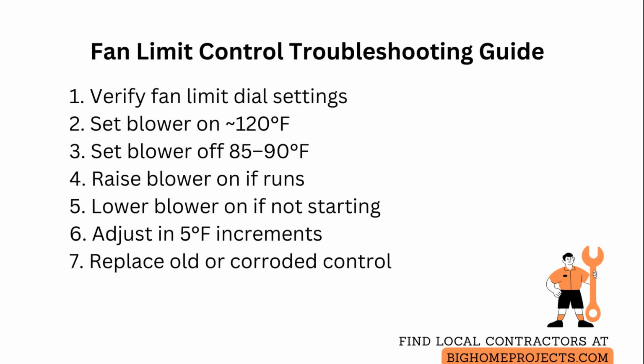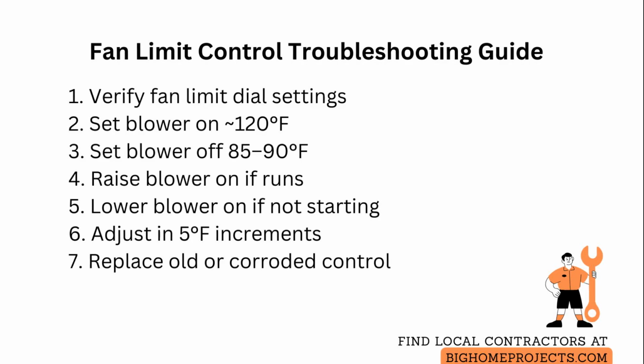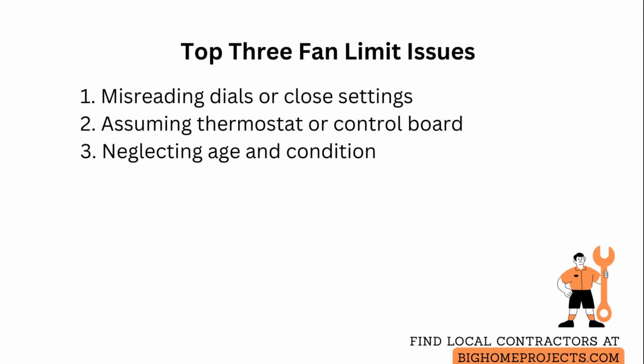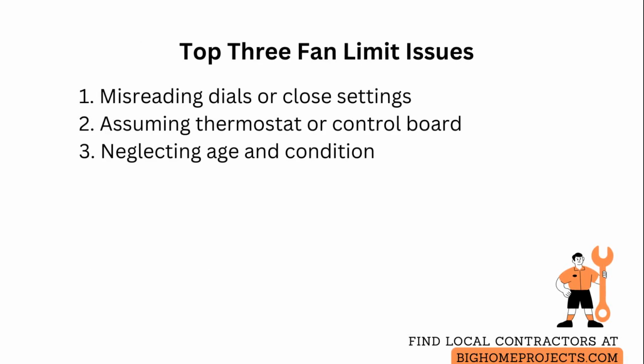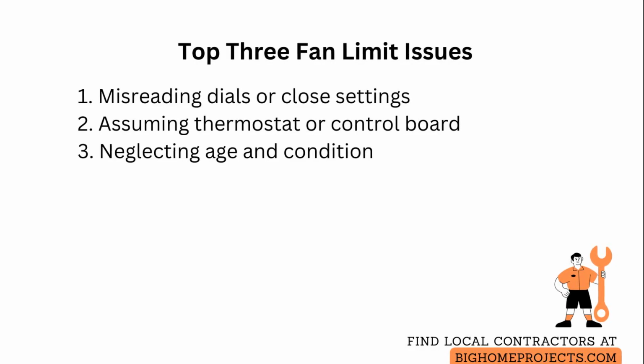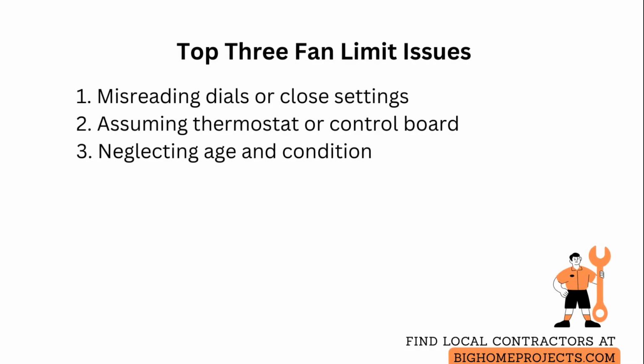If the control is old, shows corrosion, or responds erratically despite correct settings, replacement with a new fan limit control is the most reliable fix. Common mistakes include misreading the dials or setting values too close together, which can cause short cycling. Keep at least 30 degrees separation between the blower off and blower on settings to prevent rapid switching.